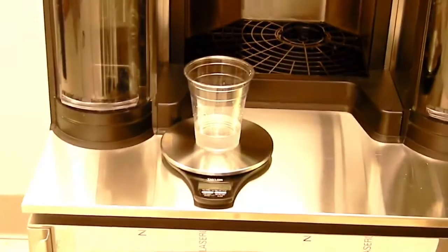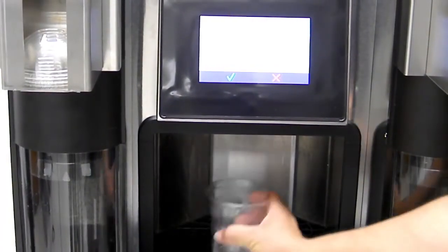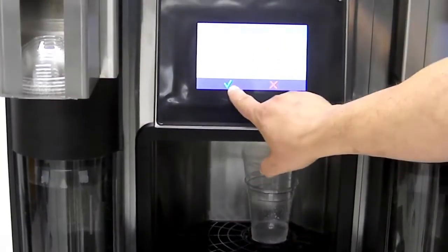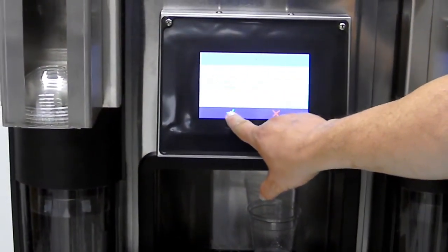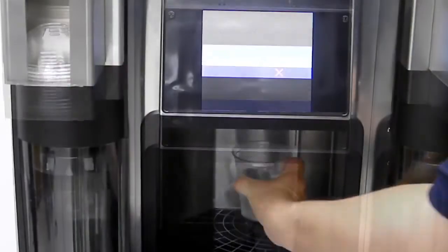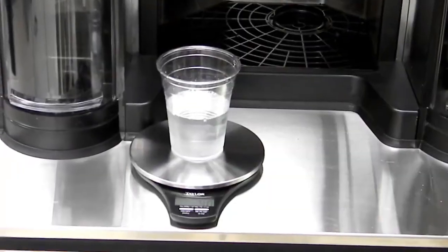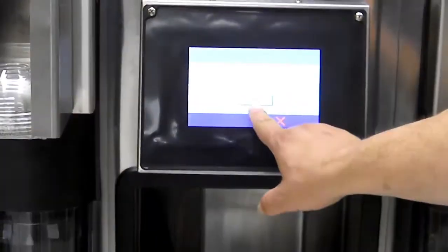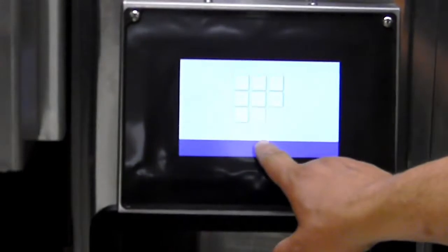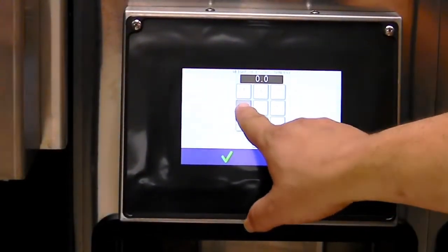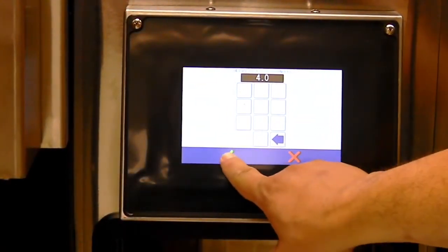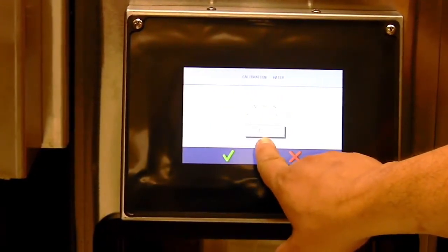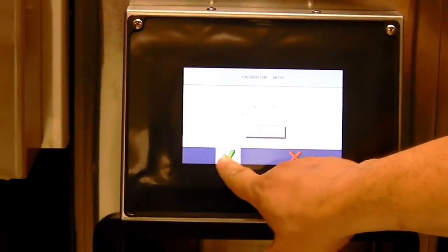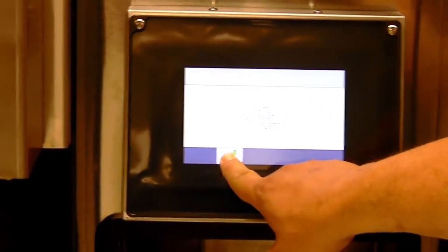We're still looking for 3.7 to 4.3 ounces. Zero the scale, put the cup back in place, select the green check for dispense. We'll now weigh the cup. The scale says our weight is now 4.0 ounces. Go back to the screen. We'll tap the box to enter the weight. And we'll put in 4.0. Hit the green check. Verify it did accept 4.0. Green check again, and our water calibration is complete.